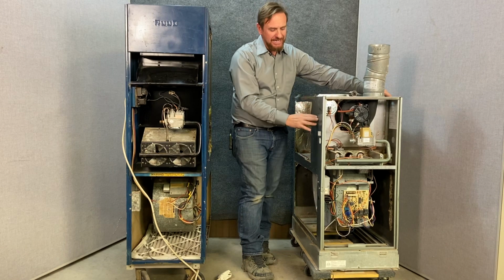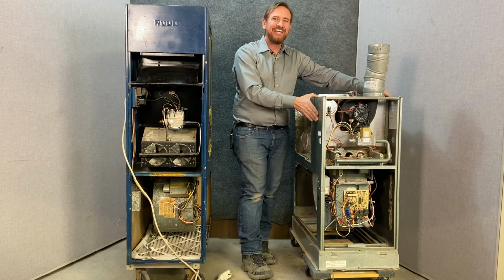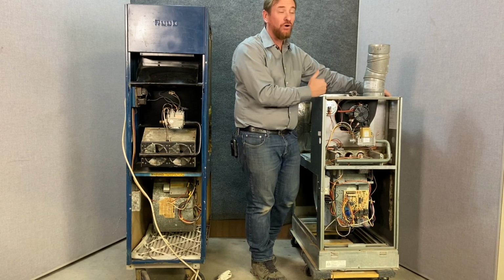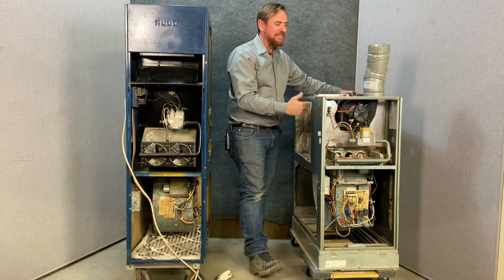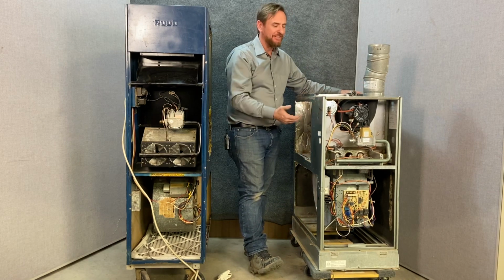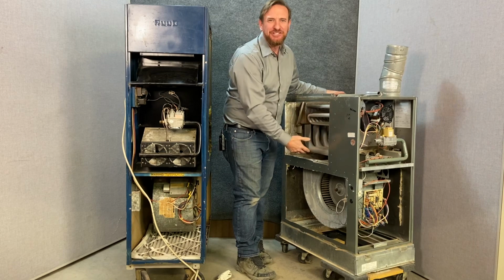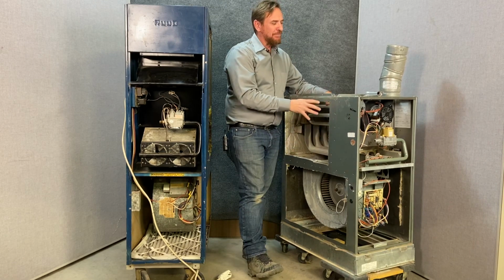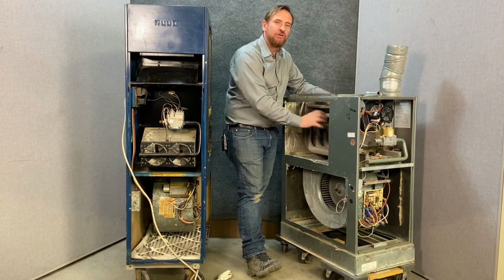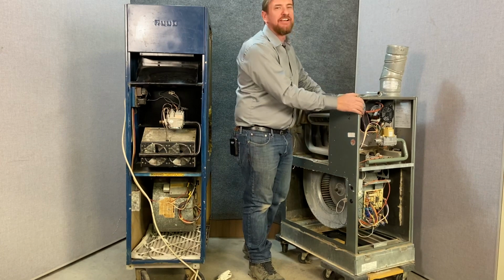But this furnace right here was manufactured in 1999. So this furnace is 21 years old as of today. But still, I wouldn't have an issue keeping this furnace running. Well, maybe not since I cut a bunch of holes in it. But if this furnace was fully operational, I wouldn't have any issues. As long as there's no holes in the heat exchanger, it's still a very safe furnace.